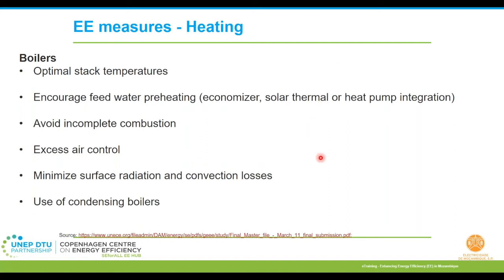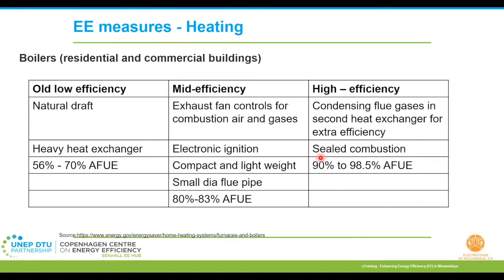So these are the different conditions which you can look into to avoid excess losses and improve your efficiencies. For residential and commercial buildings, there are three classifications: low efficiency boilers, mid efficiency boilers, and high efficiency boilers. Based on that classification, you have different information here. For mid efficiency, you will be using additional blowers or fans to control the combustion air and gases. For higher efficiency, it also uses an additional heat exchanger where it condenses the flue gases and takes up the extra heat before losing it to the atmosphere.